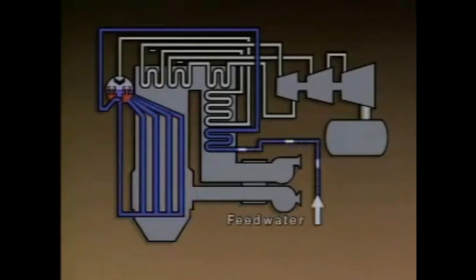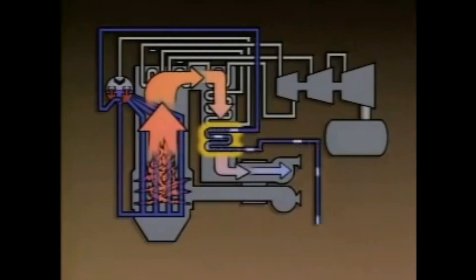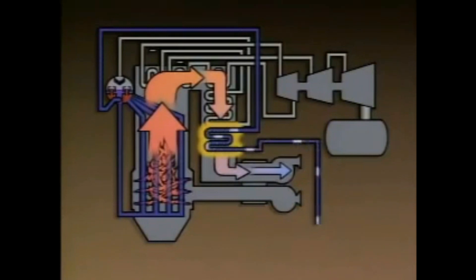The water that is supplied to a boiler is called feed water. The first component that the feed water passes through is the economizer. The economizer uses heat from combustion gases that would otherwise flow out of the stack to heat the feed water. Heating the feed water means that less fuel has to be burned in the furnace to convert the water into steam.